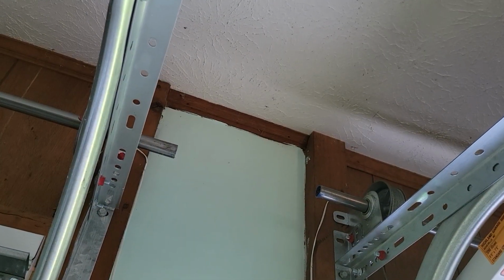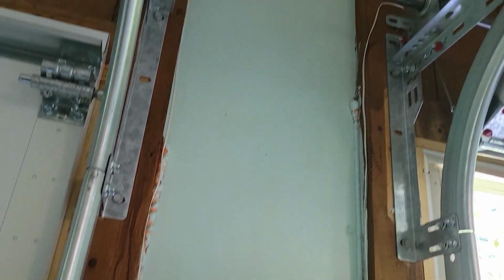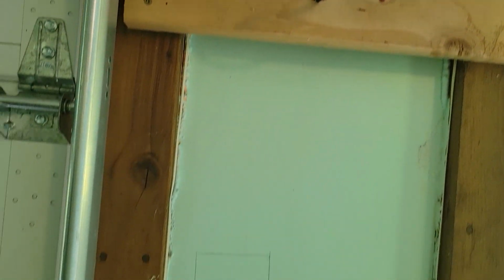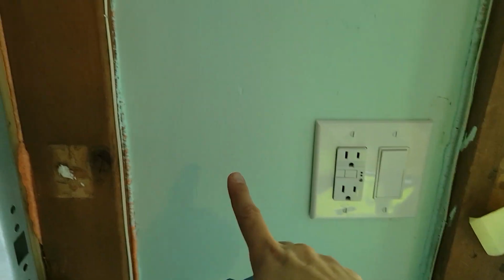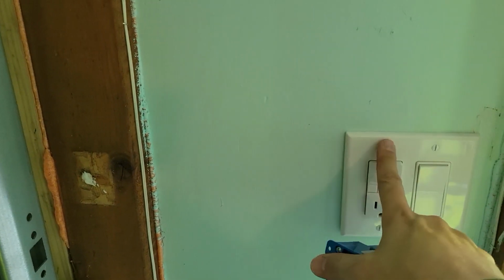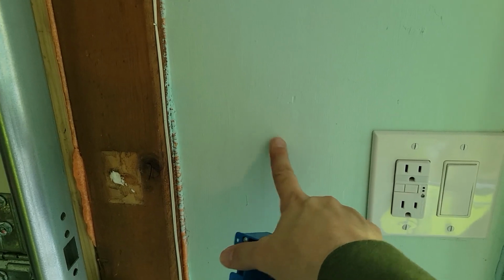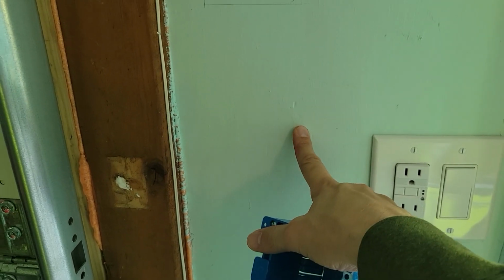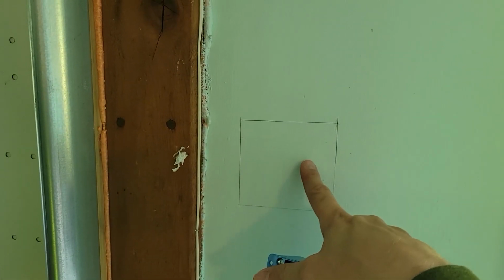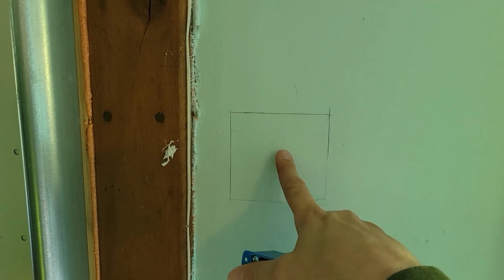As we know from earlier, we have 25 feet of 6/3 cable coming down behind this wall. Ideally you might want to bring it all the way down here so it's next to the other outlet, the 110 outlet, but I have a feeling it's going to end up being short, so I'm going to put a hole here.